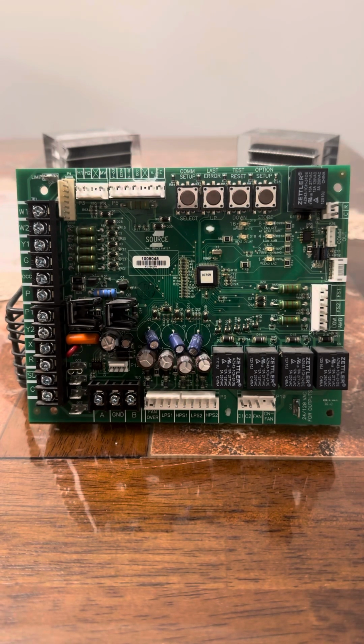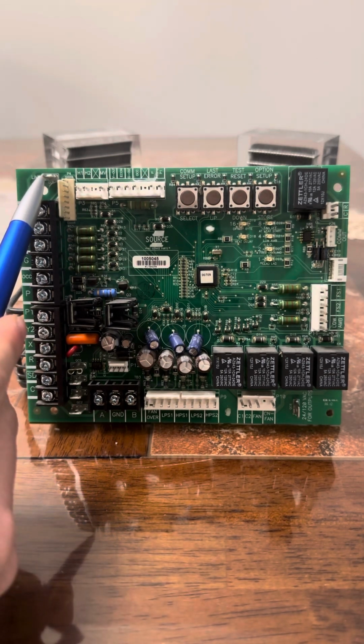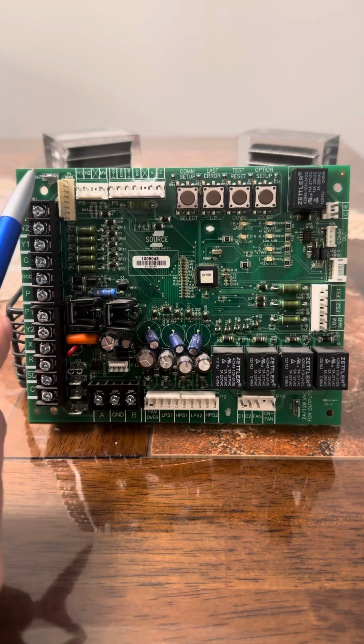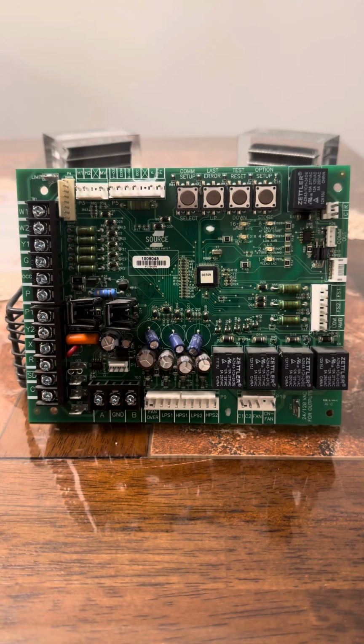And usually what will happen when you do get a 9 flash code is it means that you have lost 24 volts to this limit terminal up over here in the corner where it says limit right here. You've lost 24 volts there 3 times within an hour. And when that happens, this board is programmed to lock in the blower motor, the blower fan contactor, and it'll lock it in until the power is reset.